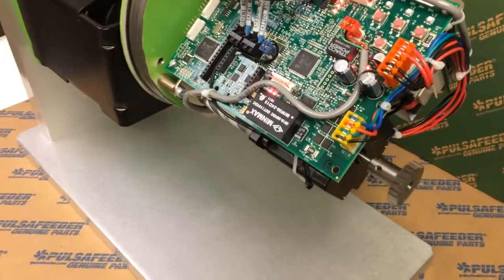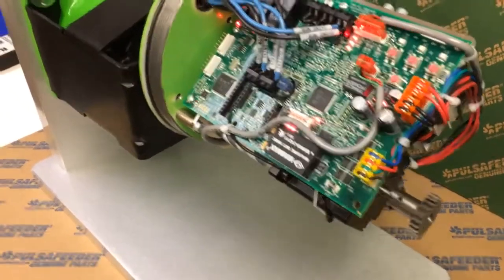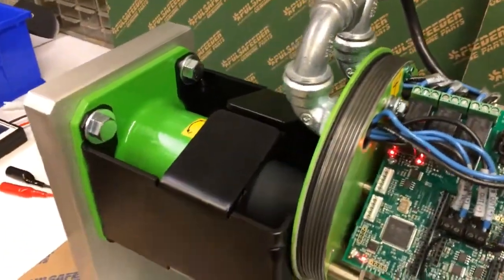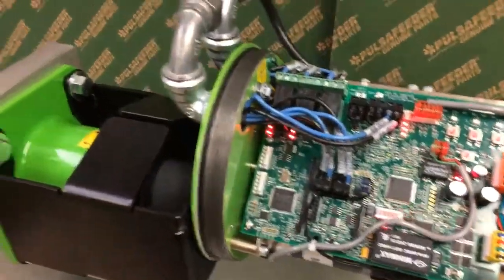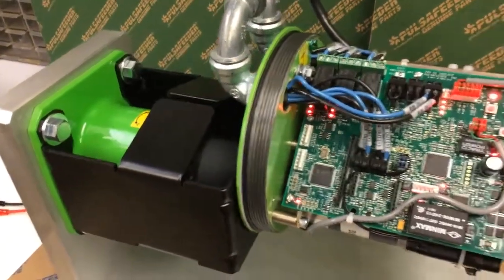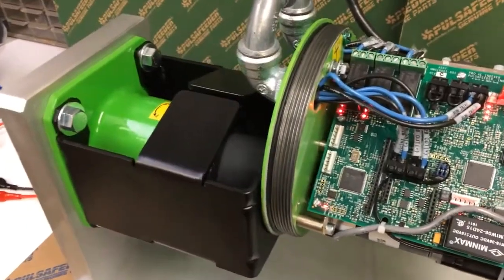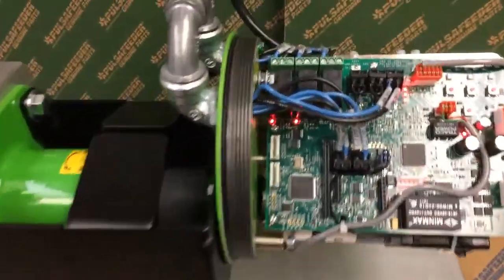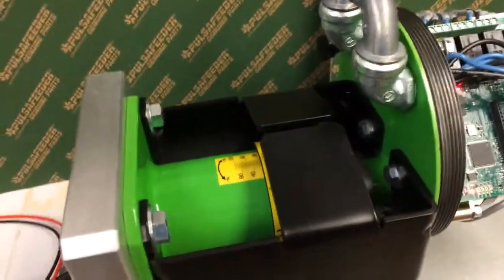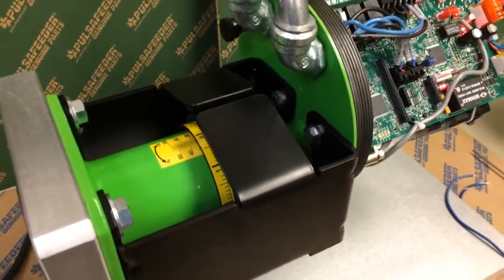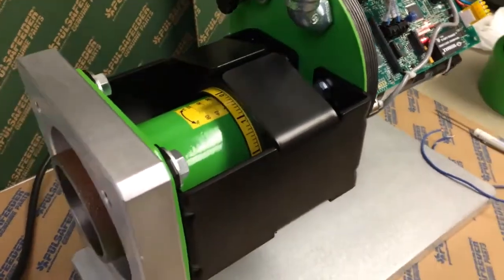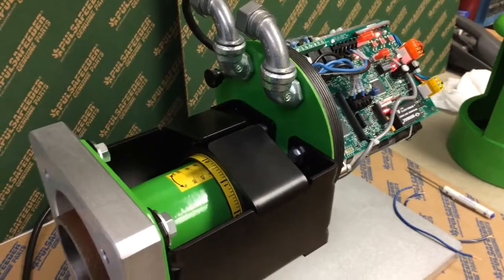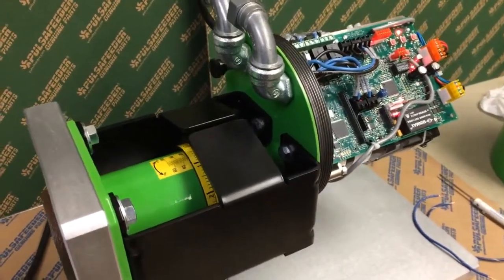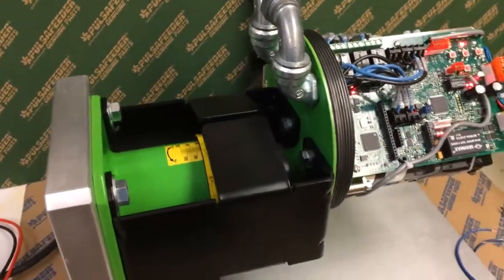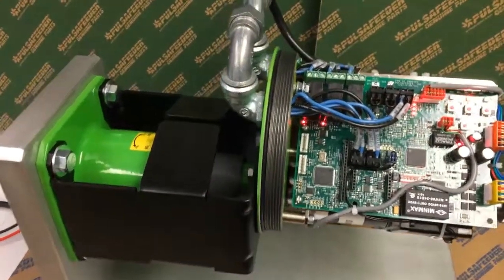I'm going to press the mode button again under the flashing LED. And now we're going to make a slow movement for about a turn and a half of the knob. We're just going to monitor the feedback mechanism and make sure that everything is working okay and aligned properly. Once we get past that point, we're going to move on up to the 100% point. So we just need to wait for that to finish. Alright, we're done with that controlled movement. Now we're going to make a fast move up to the 100% position.